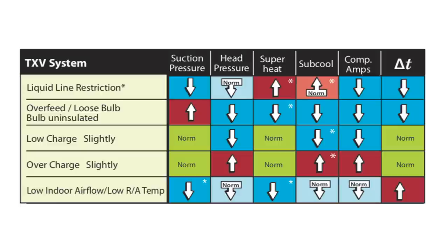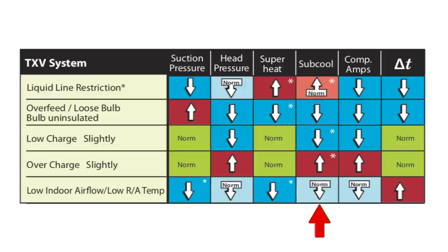Let's go through them all very quickly. When you have low airflow, you're going to have low suction pressure, low to normal head pressure — it does depend on what the outdoor temperature is — and superheat is going to be low. Subcool is going to be normal to low, and compressor amps are going to be normal to low.